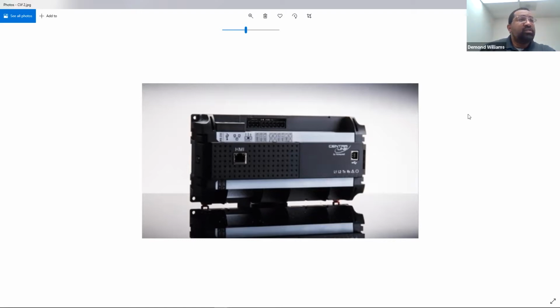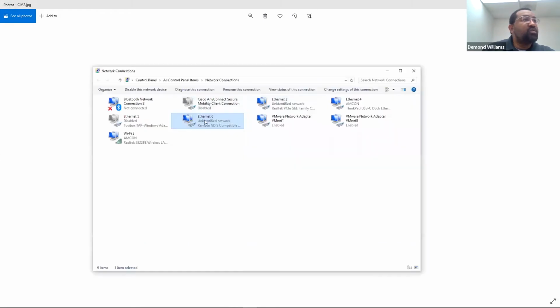One of the things is to easily connect to it. You will basically connect to this USB port right here, and you will plug it into your laptop. Once you do that, the Clif controller itself will establish a virtual Ethernet connection on your computer, which would actually create a new Ethernet network. It automatically assigns your IP address to this Ethernet port. You cannot change the IP address or anything like that, either from the Clif controller or from your computer when you are using your USB cable.